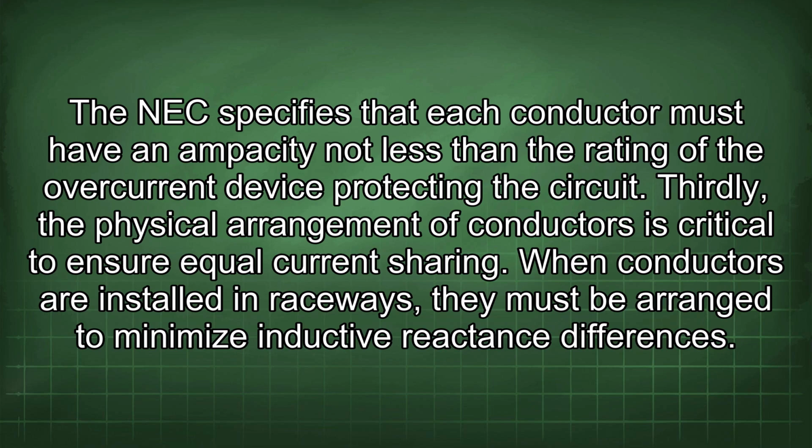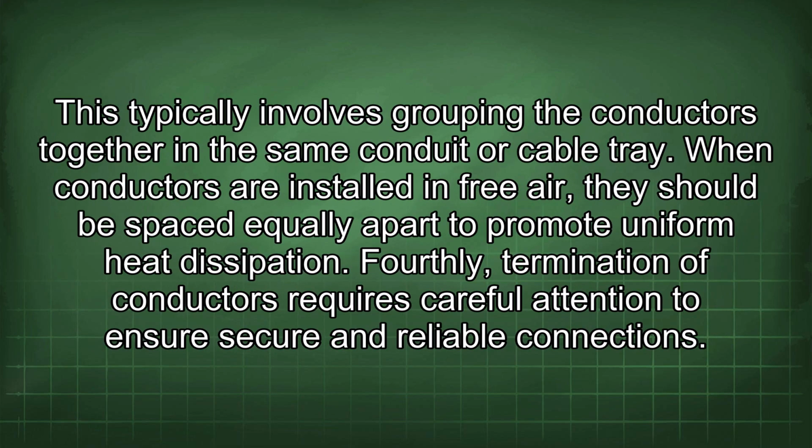When conductors are installed in raceways, they must be arranged to minimize inductive reactance differences. This typically involves grouping the conductors together in the same conduit or cable tray. When conductors are installed in free air, they should be spaced equally apart to promote uniform heat dissipation.